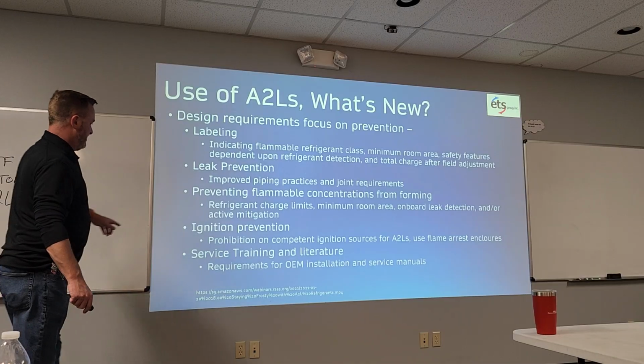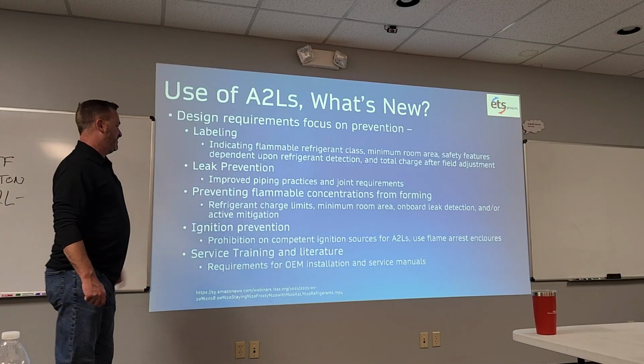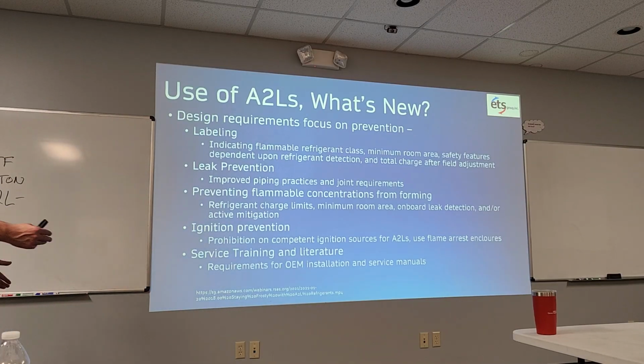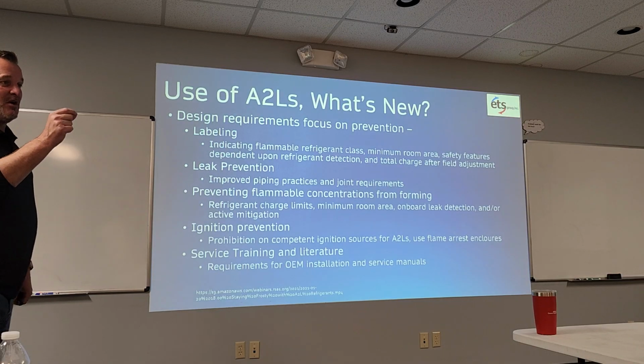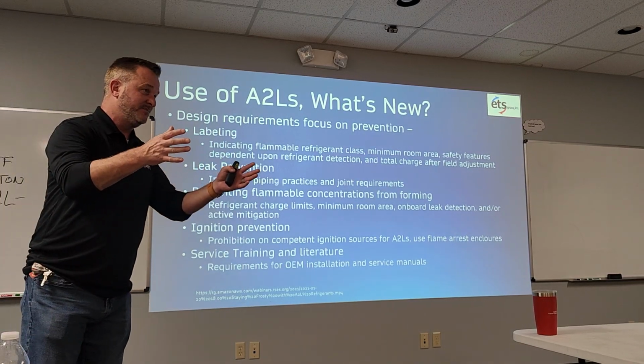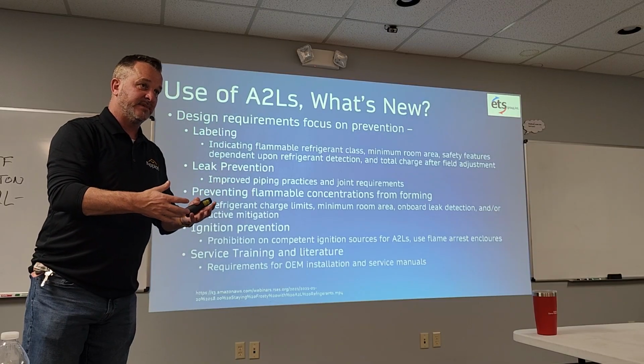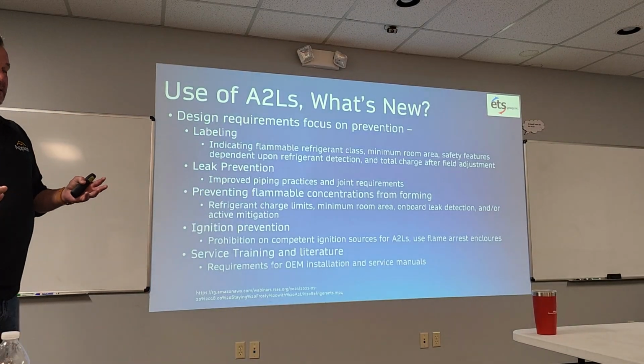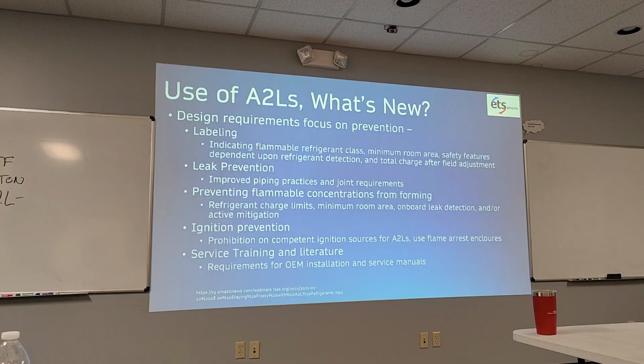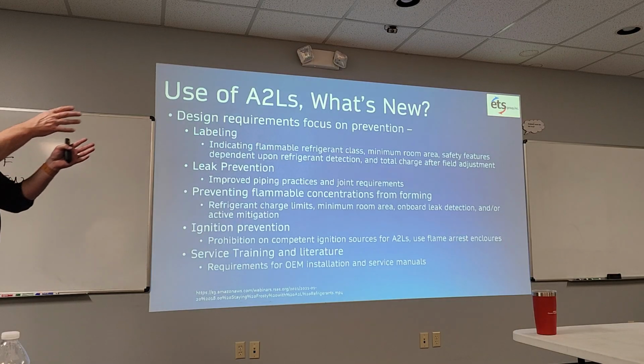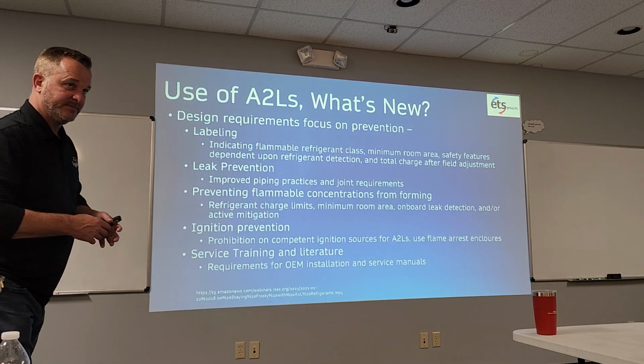And this is the big one, ignition prevention, right? So, prohibition of competent ignition sources for A2Ls, they're using flame arrest enclosures. Meaning every little spark place that could possibly be on that system is now completely enclosed, all right? That was the big thing. So we've got our practices using this refrigerant, and so on and so forth, but really it came down to what the OEMs were doing with their systems, okay?